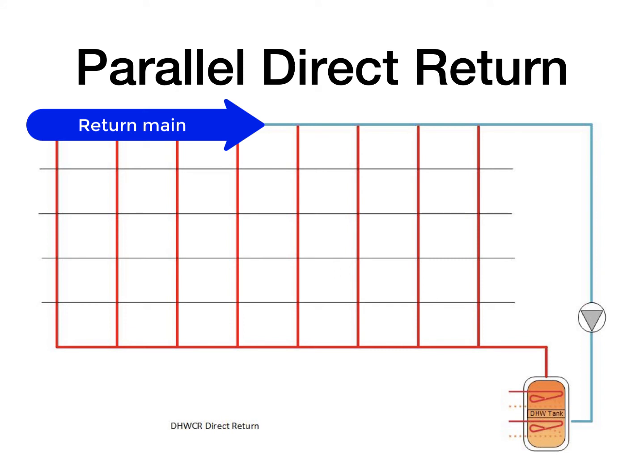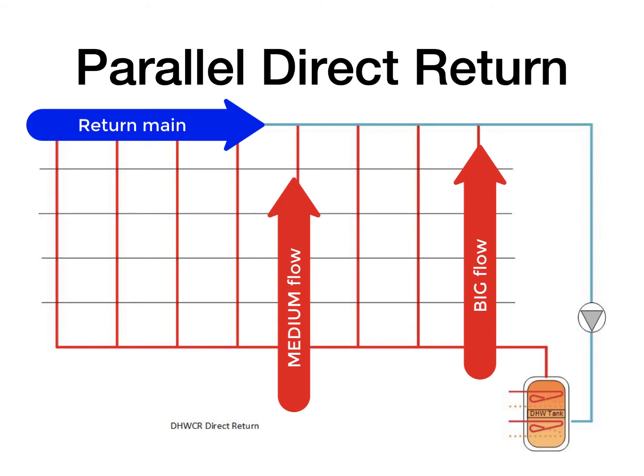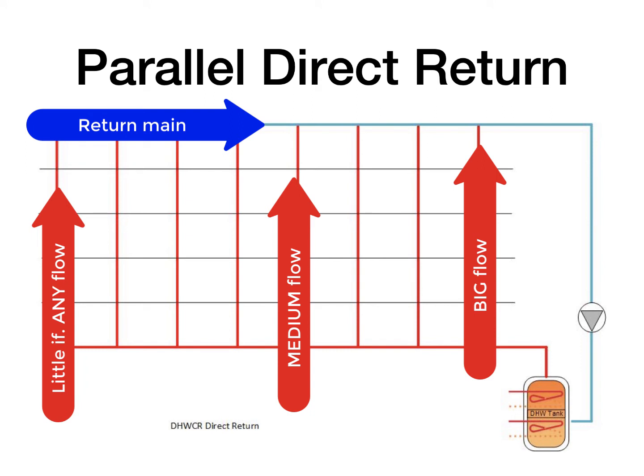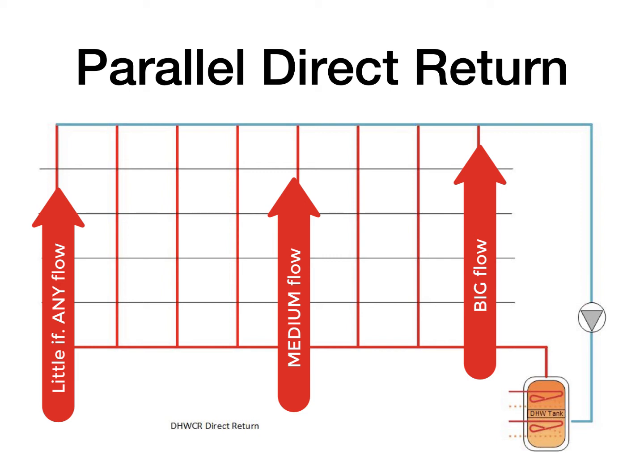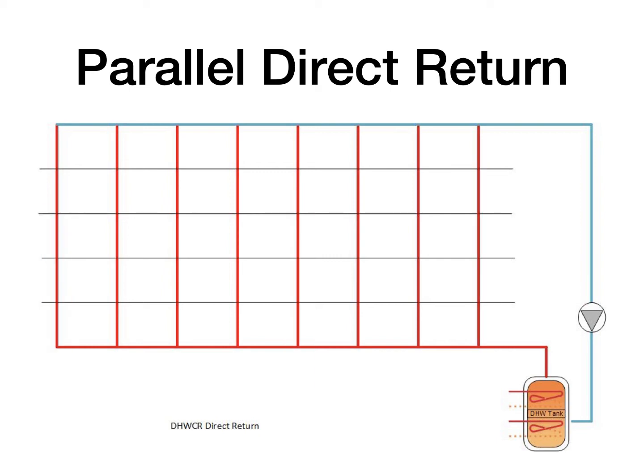Water, being wet, lazy, and stupid, is going to have a tendency to follow the path of least resistance, so that those branches that are on the left-hand side are going to have a tendency to flow significantly less than those branches that are on the right-hand side. One potential solution to the problem of the water flowing through the path of least resistance would be to install a thermal balancing valve like a Caleffi at the very top of each one of these hot water supply risers, so that as the hot water gets to that riser, the valve pinches down to its minimum setting and allows the flow to be balanced throughout the system as a whole.